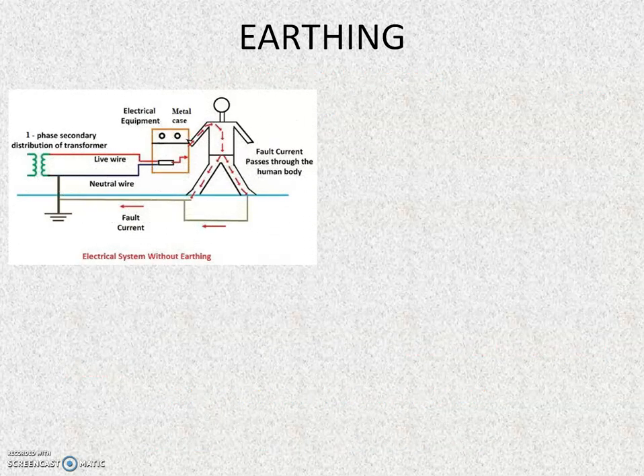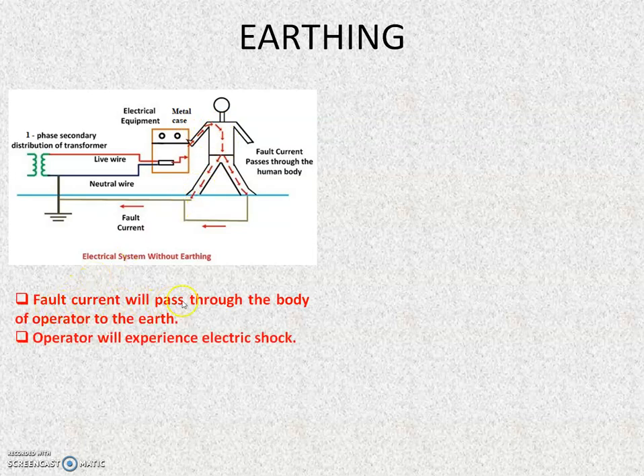Now let us see how earthing in an electrical equipment protects the user or the personnel operating the equipment. I have already discussed the case where there is no earthing. What happens if there is a leakage or a potential appearing on the metal case? If someone unknowingly touches that case, current will take a path through that person and he will experience an electrical shock. So fault current will pass through the body of the operator to the earth and the operator will experience electric shock and it may cause even death.